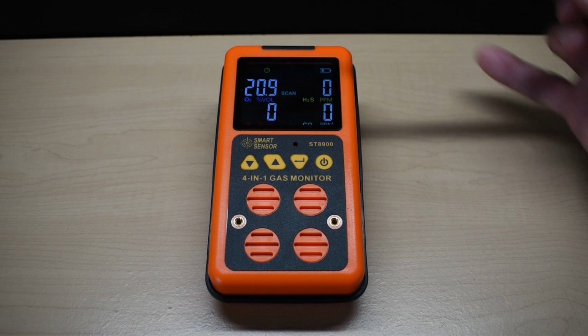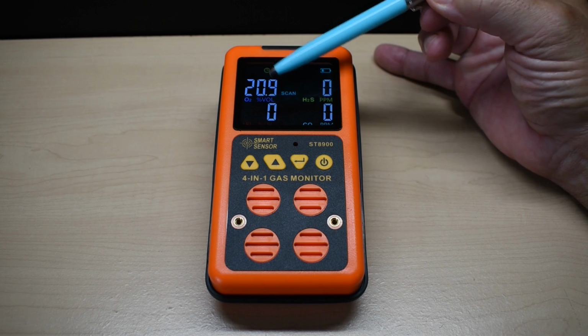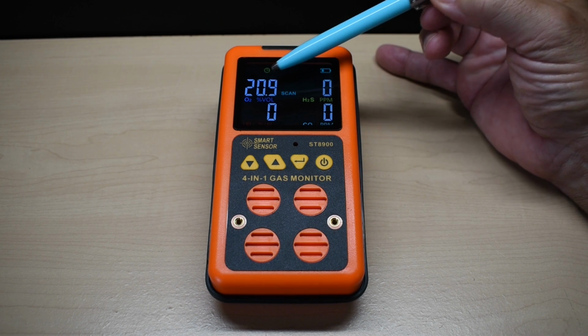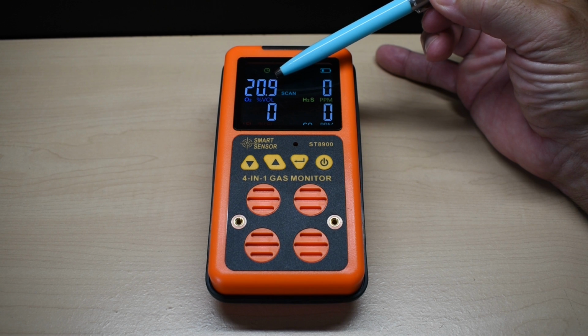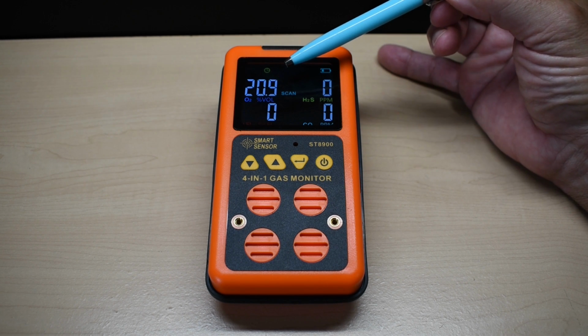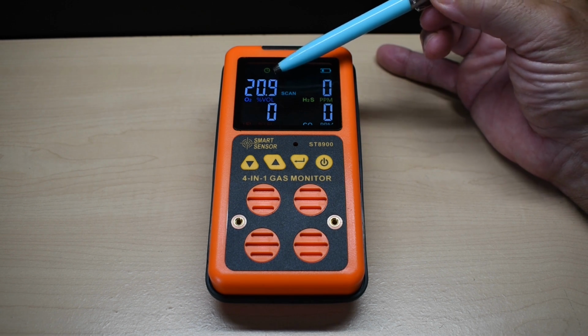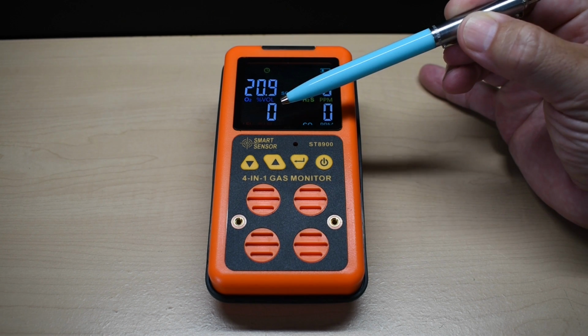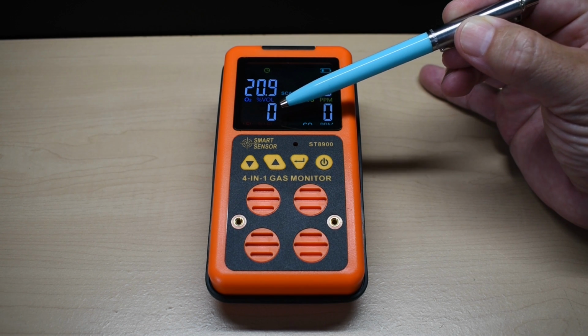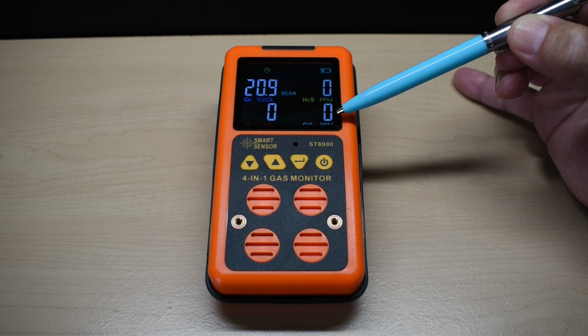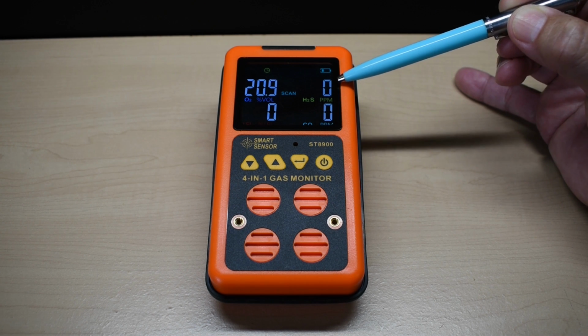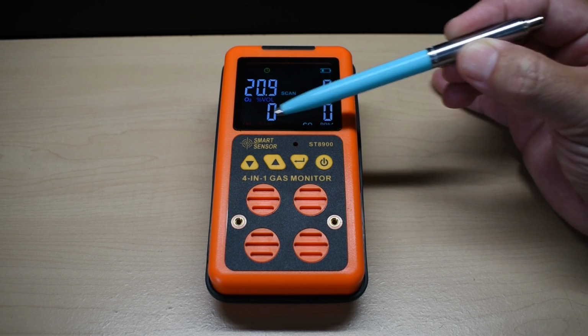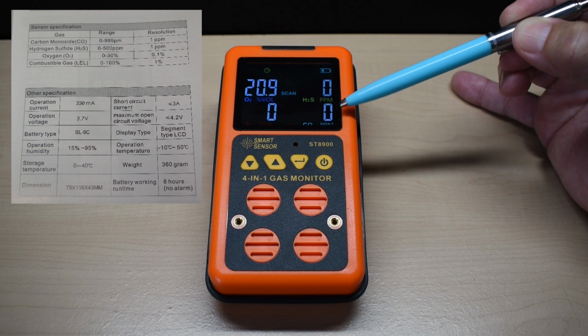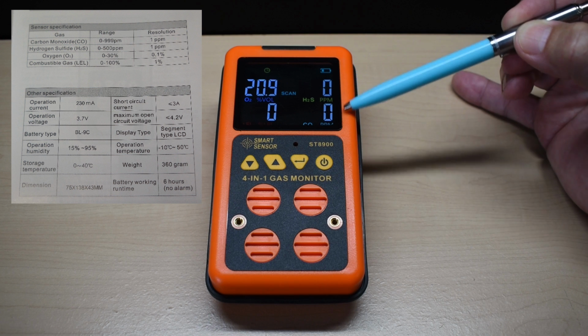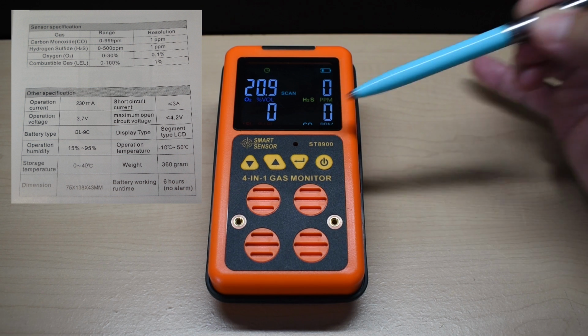When I got this, this was the one thing I had to recalibrate, and it was very simple to do. It was coming in around 18.5 and the alarm was going off. So I'm going to show you what to do to set it properly. And these 3 here, the LEL, lower explosive limit, carbon monoxide, and the hydrogen sulfide, you do not want to adjust the settings from the factory. If you do, it's not going to be accurate. You need those test sources to properly calibrate the unit for these 3.